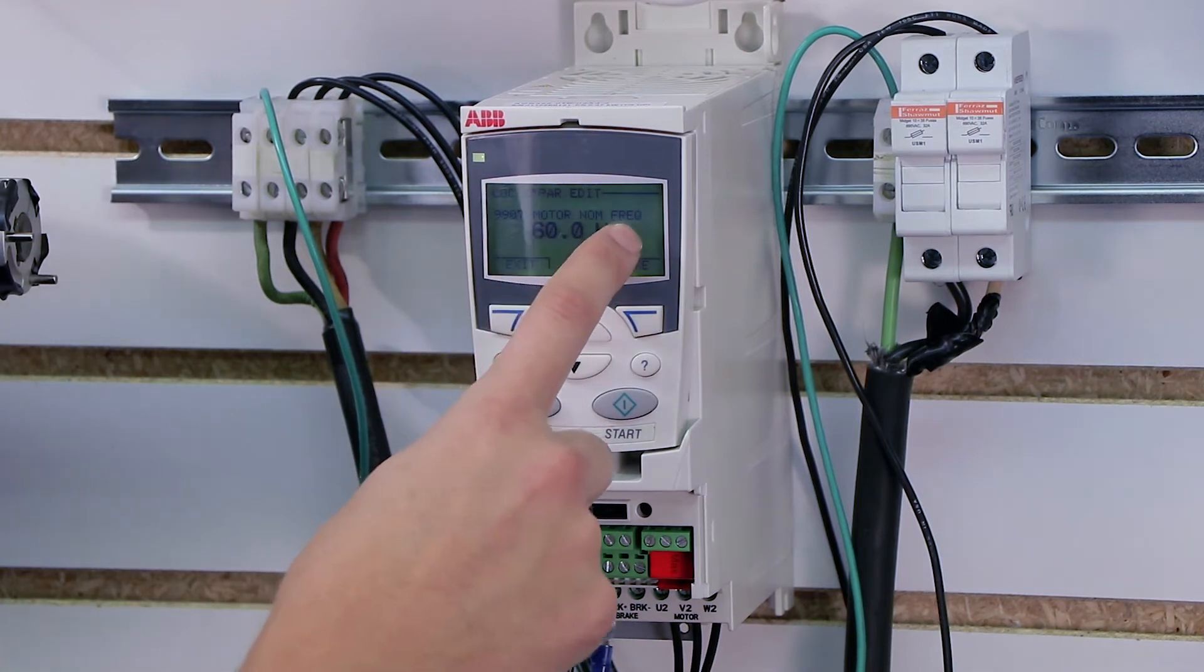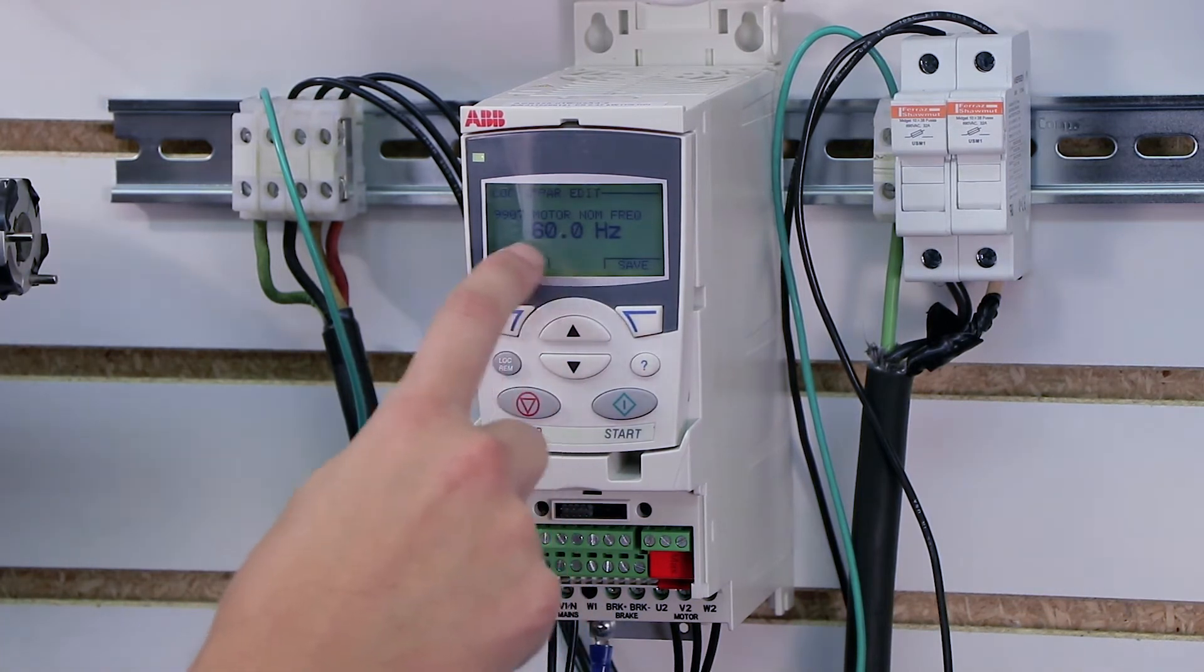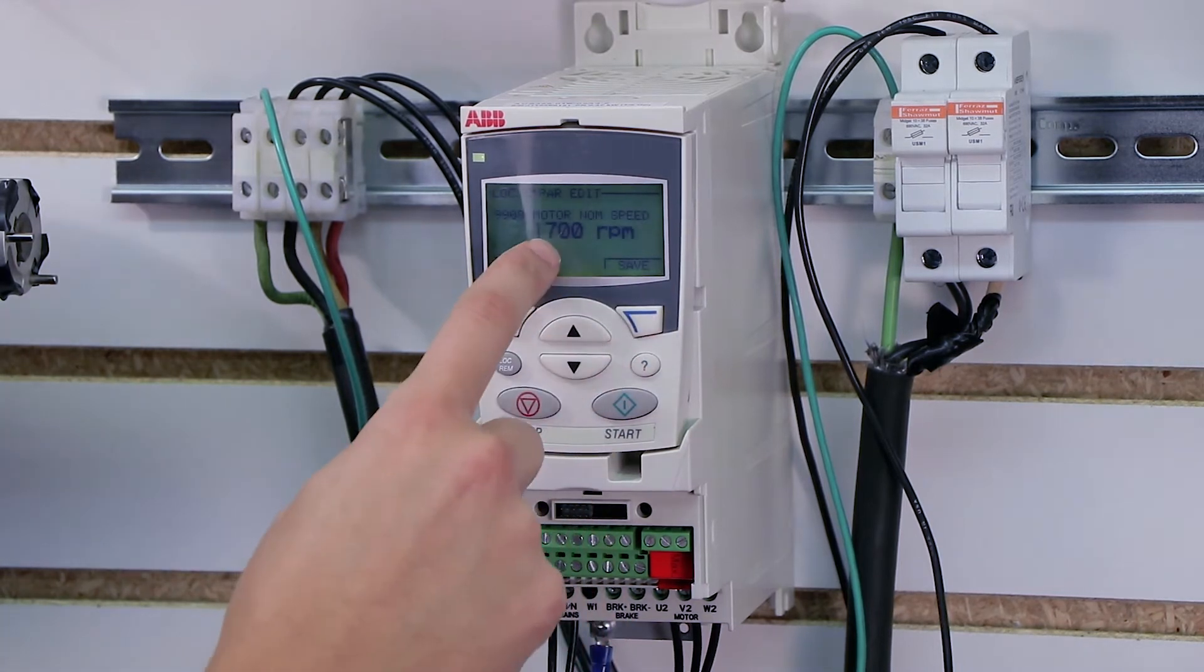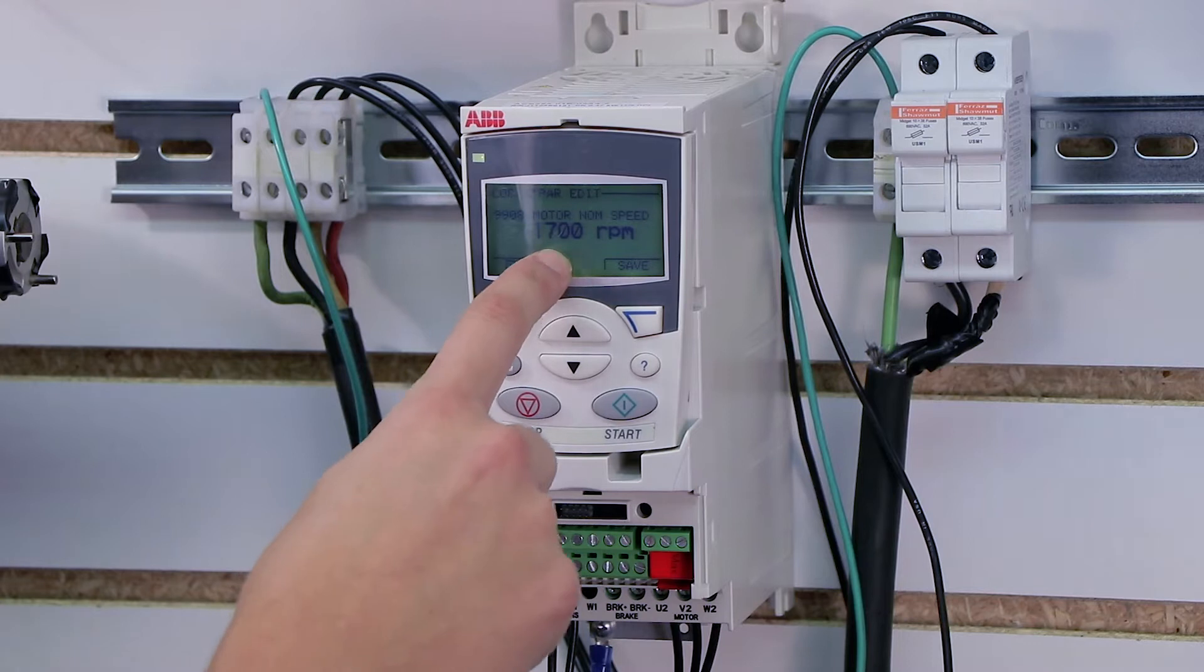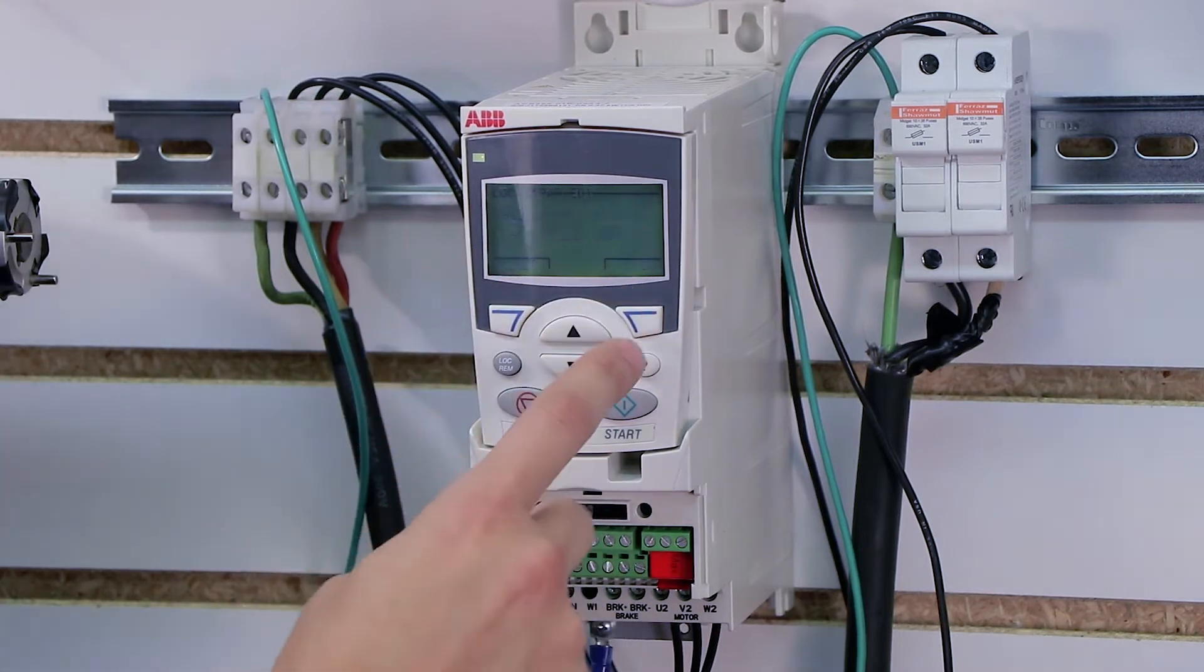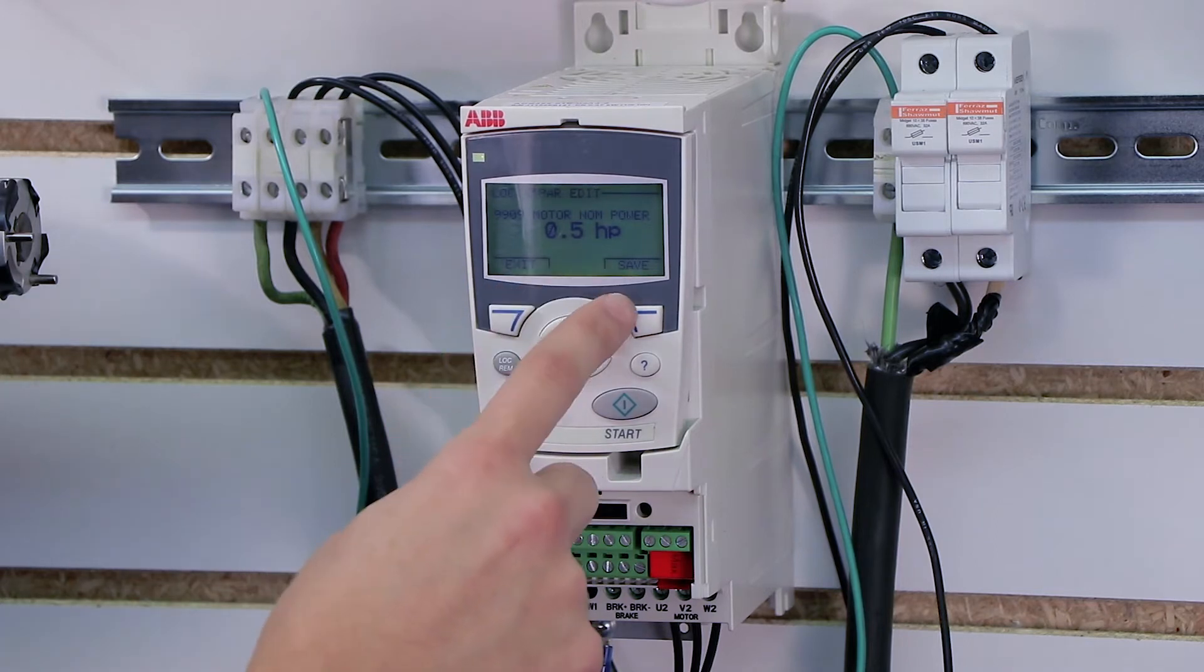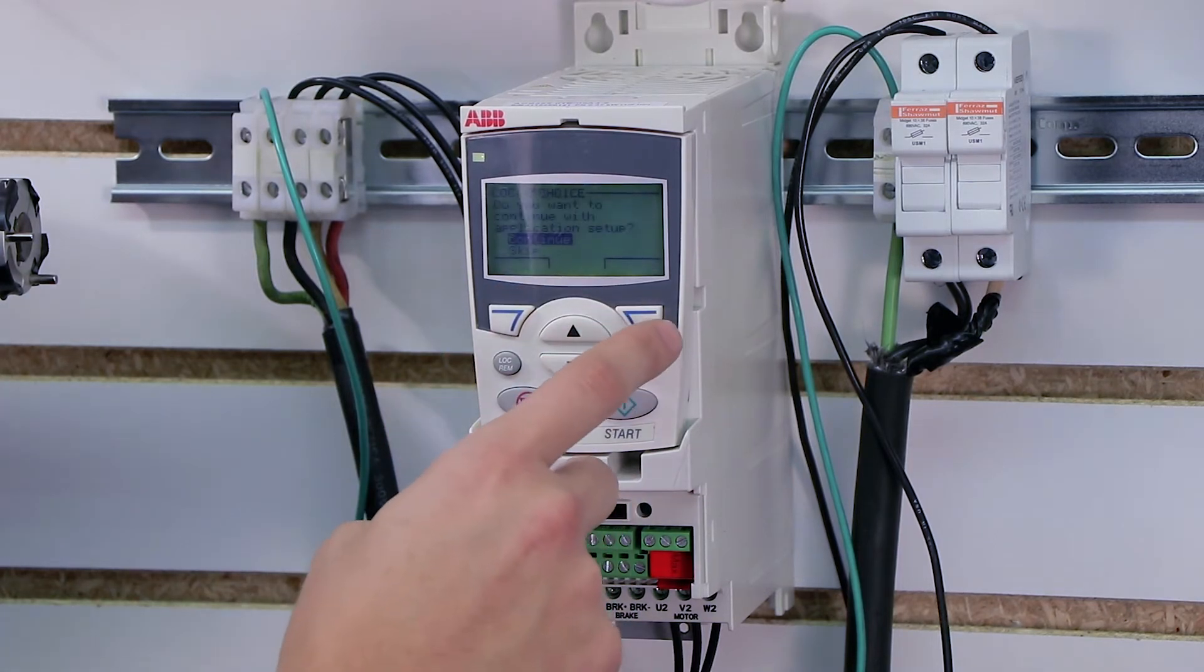My motor nominal frequency is also on the nameplate of the motor, and mine is 60 hertz. My motor nominal speed is also on the nameplate of the motor, 1,700 RPM is what mine's set for, and the nominal power in horsepower for me is a half horsepower motor, so I'm going to press enter on that.